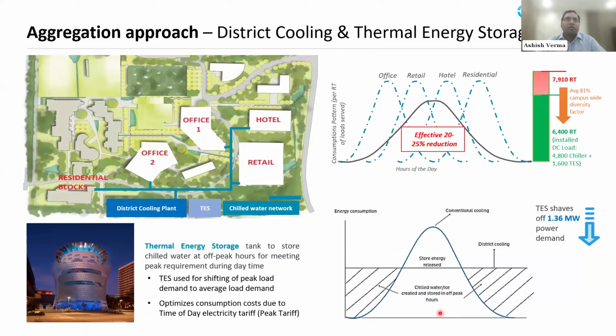I'll quickly go to the district cooling approach, which is normally a demand aggregation approach coupled with thermal energy storage. Compared to the conventional approach, we were able to meet this cooling demand of 7910 RT with an installed capacity of only 6400 RT, out of which 4800 was mechanical chiller capacity and 1600 was the thermal energy storage system. So when we install this TES of 1600 RT capacity, we are shaving off the peak demand by 1.36 megawatt. This is what thermal energy storage can benefit in this kind of mixed use development.